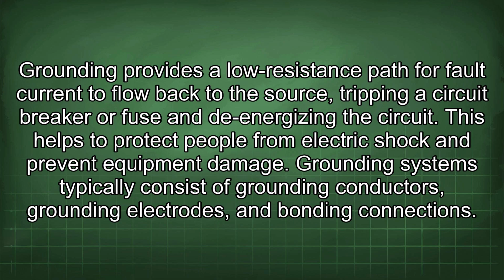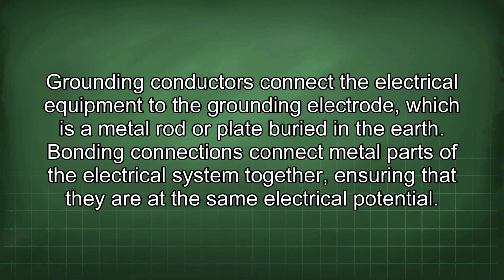Grounding systems typically consist of grounding conductors, grounding electrodes, and bonding connections. Grounding conductors connect the electrical equipment to the grounding electrode, which is a metal rod or plate buried in the earth. Bonding connections connect metal parts of the electrical system together, ensuring that they are at the same electrical potential.